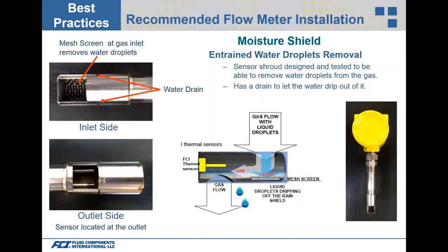Another option is a moisture shield — a shroud with a mesh screen that knocks out water droplets, plus drain holes so water drains from the shroud. The active sensing element or flow element on the outlet side stays clean because water droplets are knocked out before reaching it. This is a great option when there's a lot of water vapor entrained in the gas.